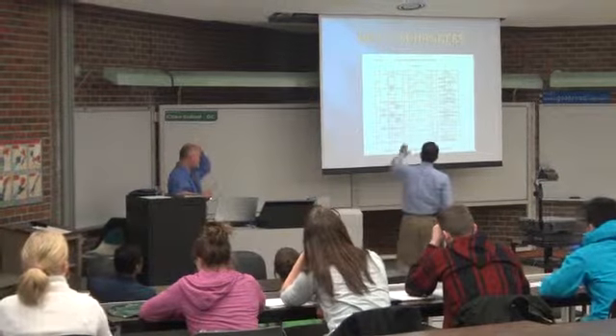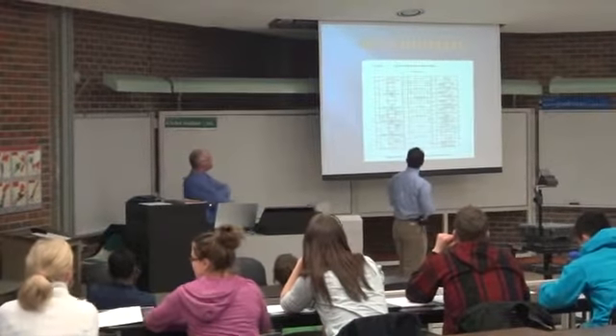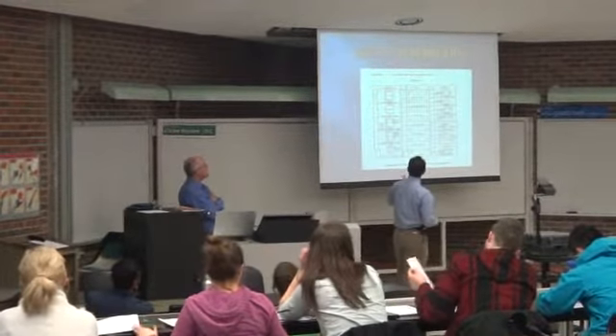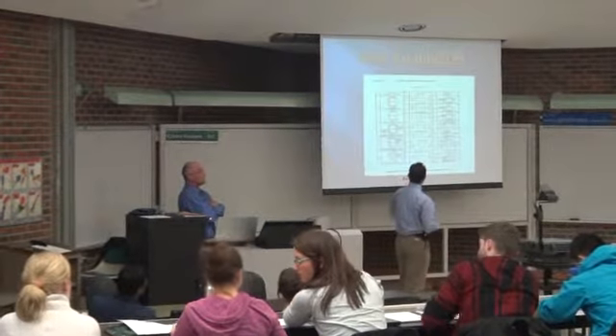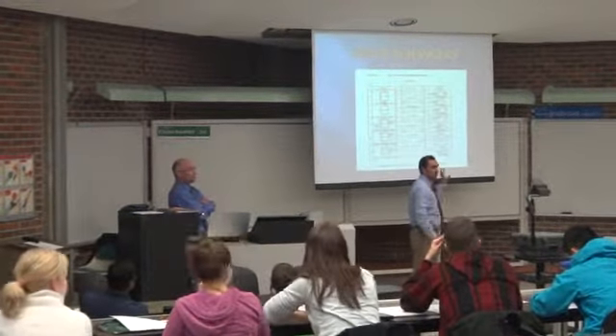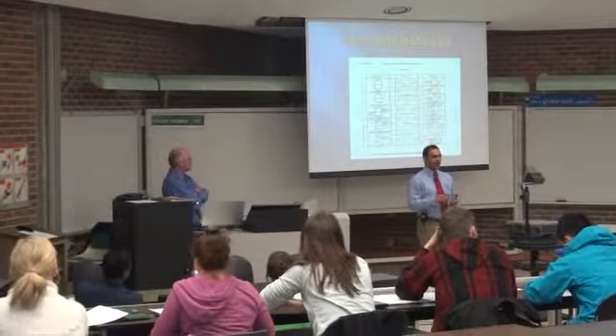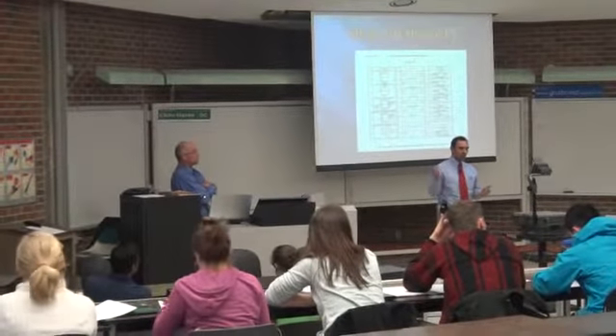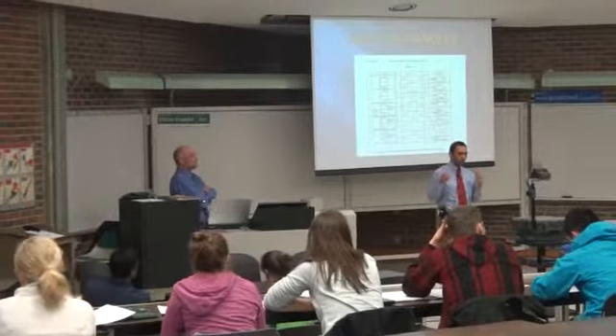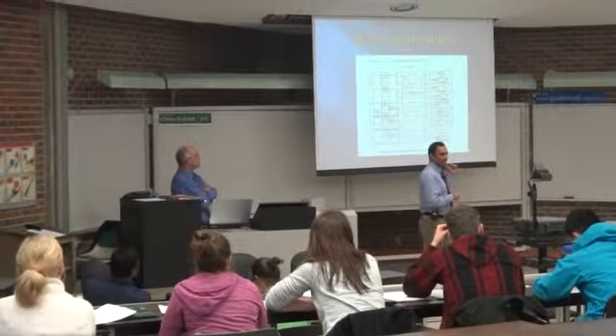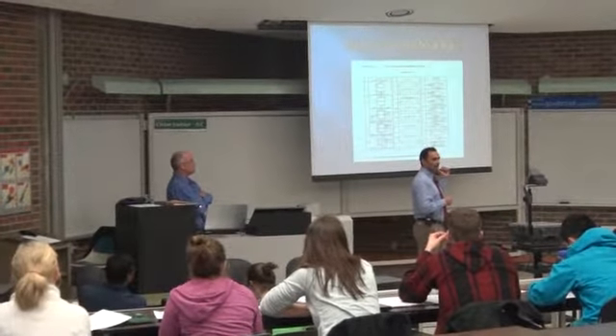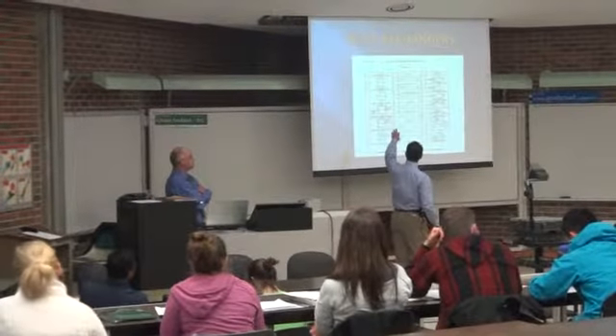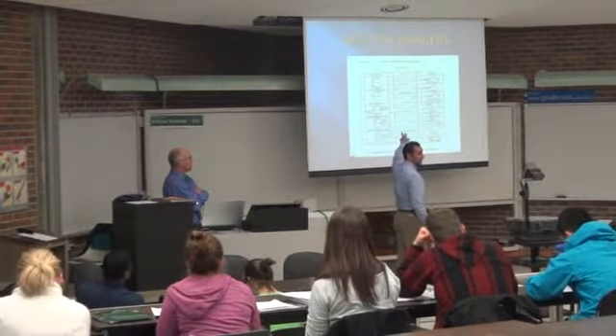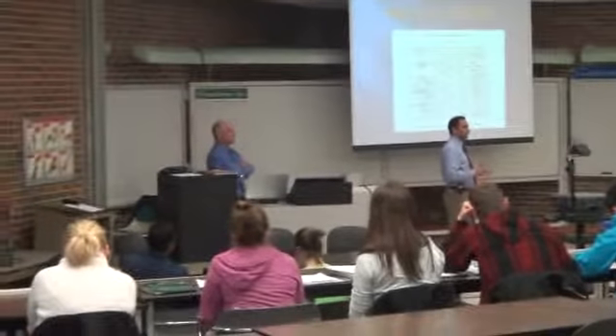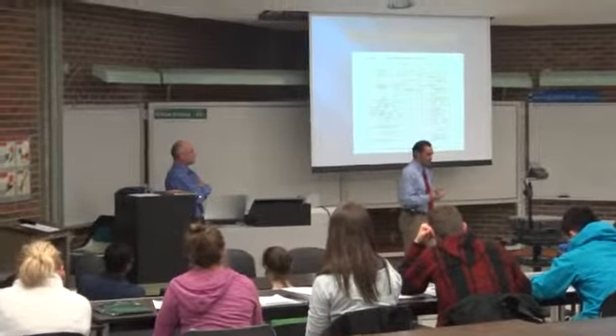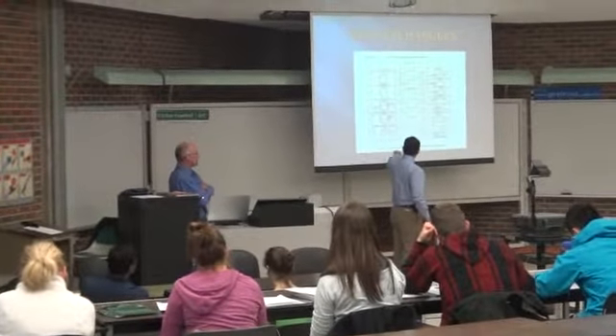So if you look, the first column, these are the front heads. It shows A type, B type, C type, N type, D type. Every head has its own importance. Like A type can be used where you want a quick inspection of the tube and you want to remove the bundle. And you can replace that with cheaper B type head because you're not putting additional flange and cover on there. You just do welding a semi-elliptical head. So depending on if you have high pressure exchanger, then you would want to use the D type head.